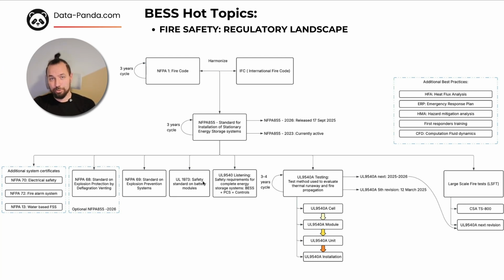Next, we'll move to product certification standards. At battery level, we're looking into UL 1973. It's commonly used as a safety standard for battery modules. One of the key certification standards is UL 9540. UL 9540 evaluates the complete energy storage system, including batteries, power conversion system, and control system. It ensures that the integrated system meets electrical and safety requirements. Another critical piece of the safety framework, and the most discussed, is UL 9540A testing.